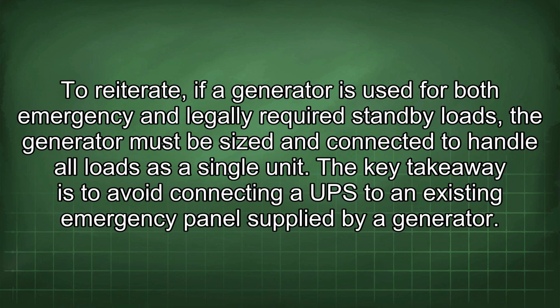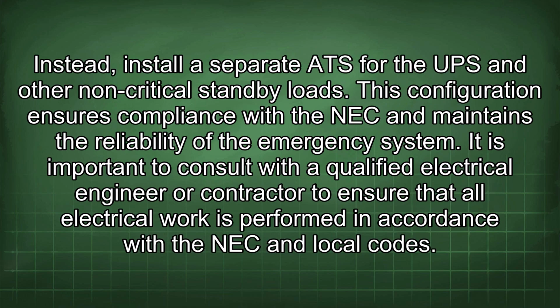To reiterate, if a generator is used for both emergency and legally required standby loads, the generator must be sized and connected to handle all loads as a single unit. The key takeaway is to avoid connecting a UPS to an existing emergency panel supplied by a generator. Instead, install a separate ATS for the UPS and other non-critical standby loads. This configuration ensures compliance with the NEC and maintains the reliability of the emergency system.